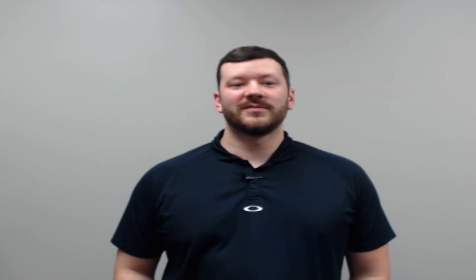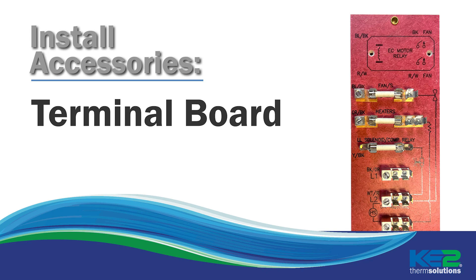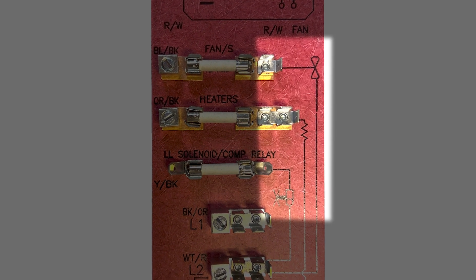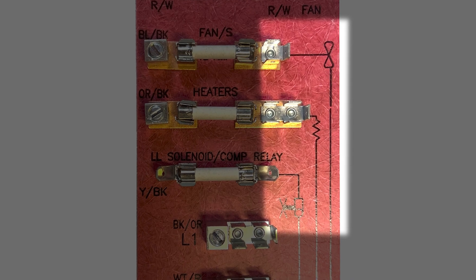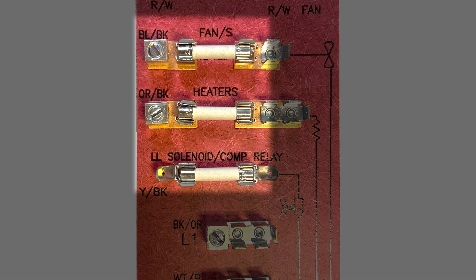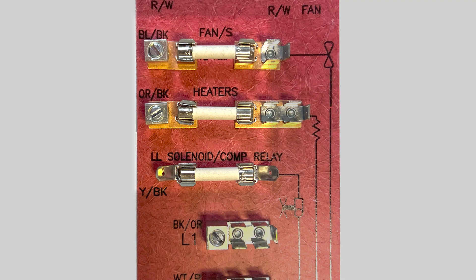Another standard component for many of our kits is the KE2 Therm terminal board. Like the other accessories, it makes installation one step closer to foolproof. The terminal board standardizes the wiring for every install and the board is marked with well-known symbols for fans, heaters, and liquid line solenoid, making future diagnostics instantly recognizable. Built-in fuses on the terminal board protect every relay on the controller from power surges. Once a component failure is identified, the controller can be up and running quickly.